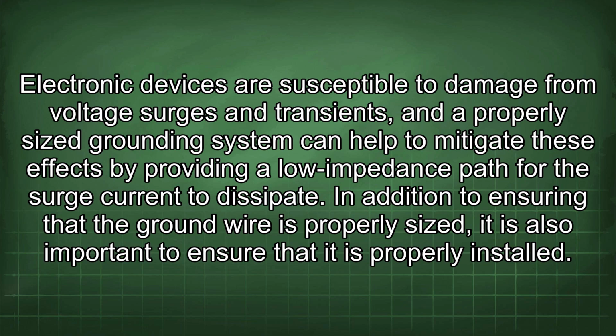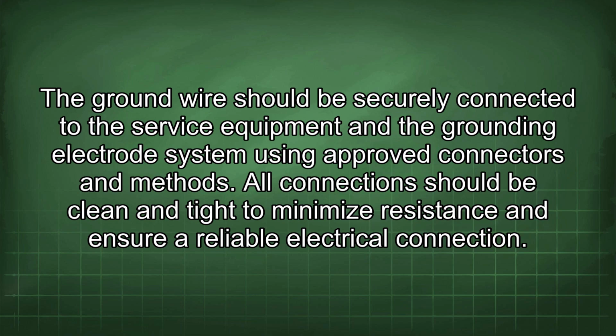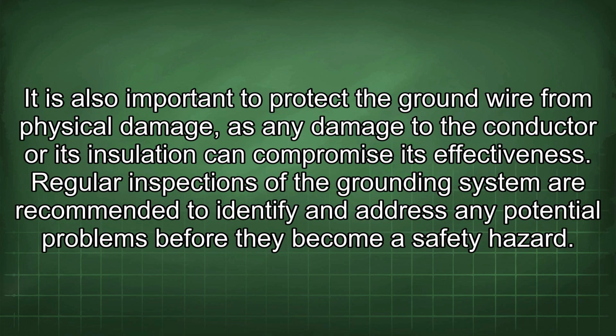In addition to ensuring that the ground wire is properly sized, it is also important to ensure that it is properly installed. The ground wire should be securely connected to the service equipment and the grounding electrode system using approved connectors and methods. All connections should be clean and tight to minimize resistance and ensure a reliable electrical connection. It is also important to protect the ground wire from physical damage, as any damage to the conductor or its insulation can compromise its effectiveness.